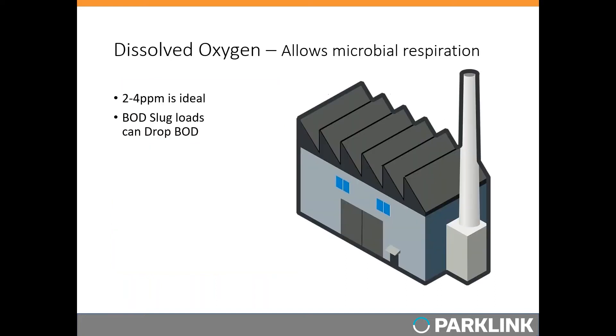The big, usually controllable factor for nitrifiers is dissolved oxygen. These nitrifying bacteria are aerobic microorganisms that require oxygen to respire and perform their oxidation to get energy. Two to four parts per million of dissolved oxygen is considered ideal. In plants with poor oxygen, it's less commonly an issue with plant design and more commonly due to poorly functioning aerators. Many plants regulate aeration basins using a dissolved oxygen probe, but sometimes the probe breaks or gives a false reading of adequate dissolved oxygen.